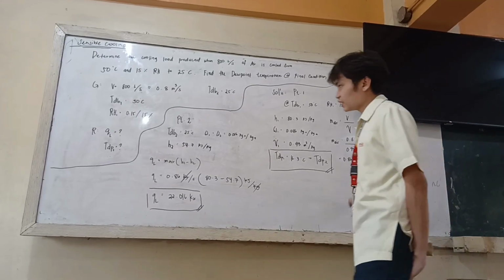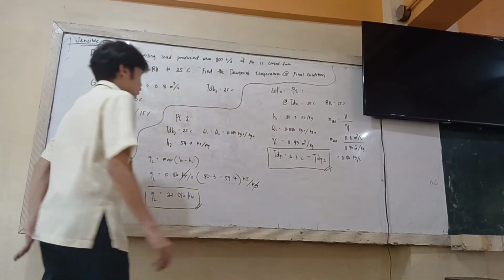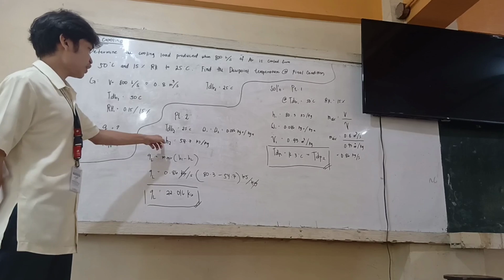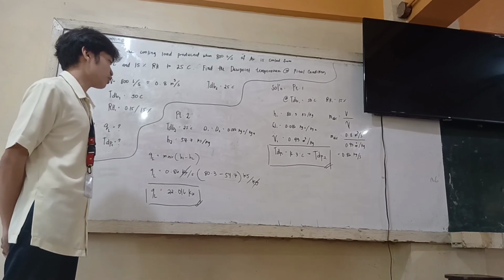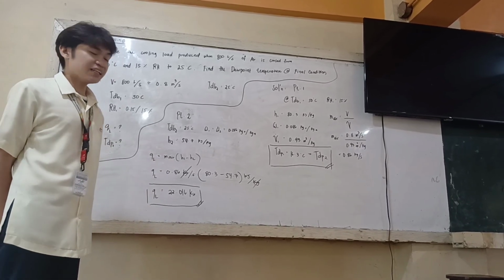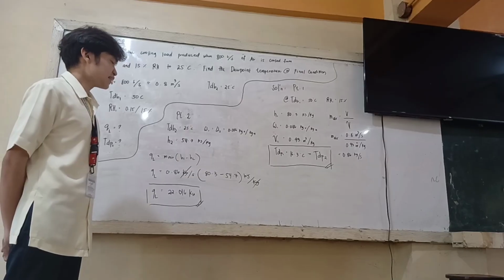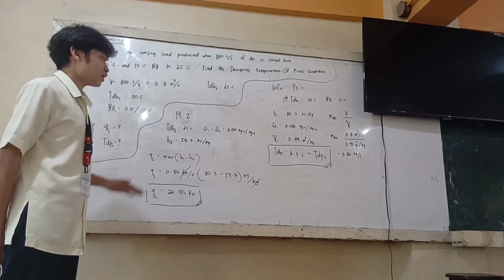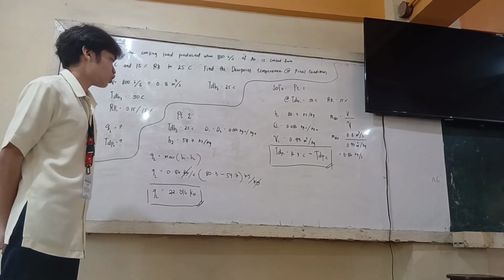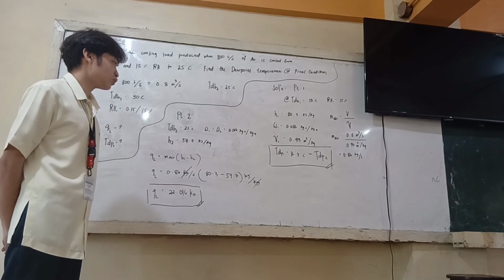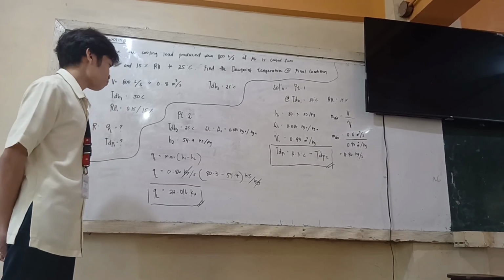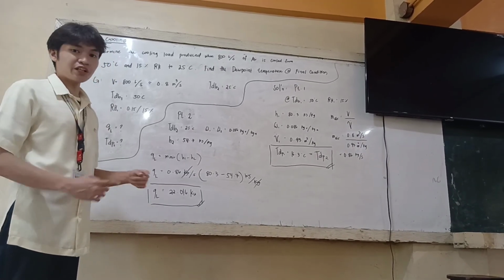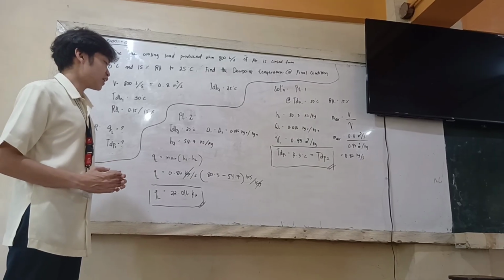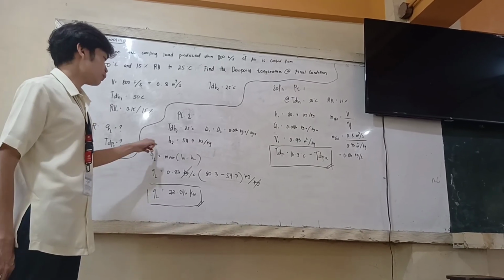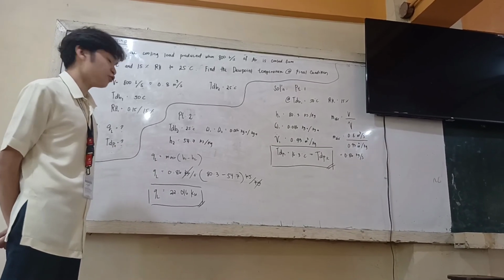Since we get this, let's move on with point 2. At point 2, we have a dry bulb temperature of 25 degrees Celsius. Since it is a sensible cooling, it has a constant humidity ratio of 0.0116. From there, we plot the points and find the intersecting point, getting the enthalpy, which is 54.7 kilojoules per kilogram.